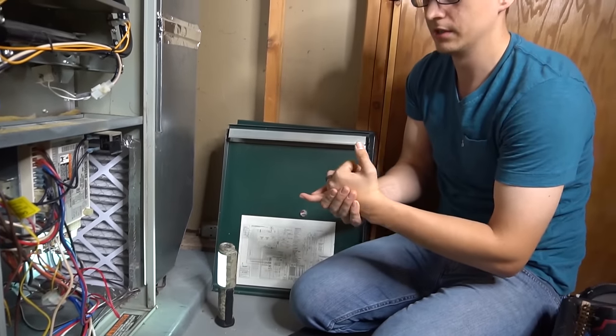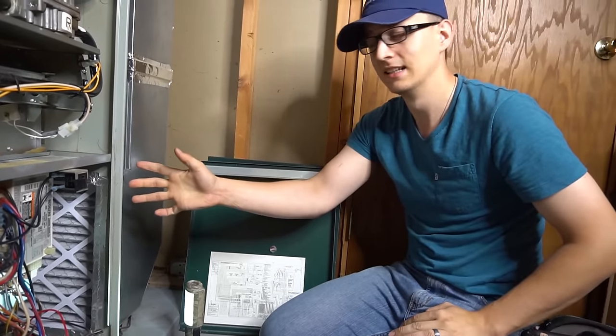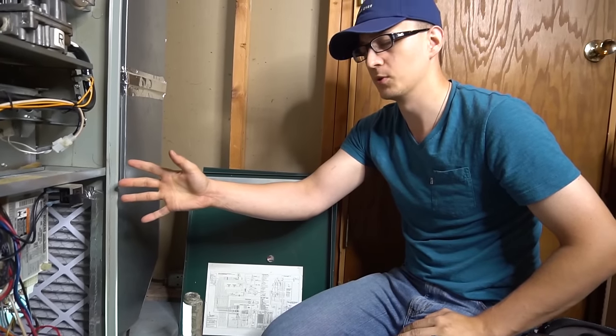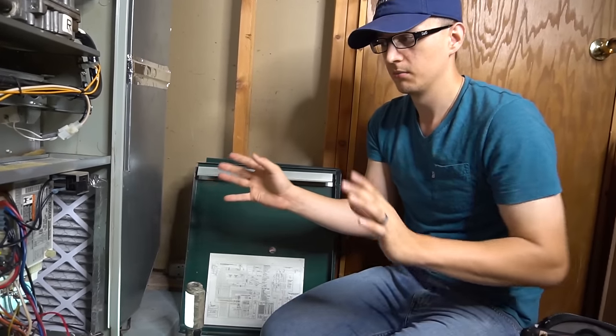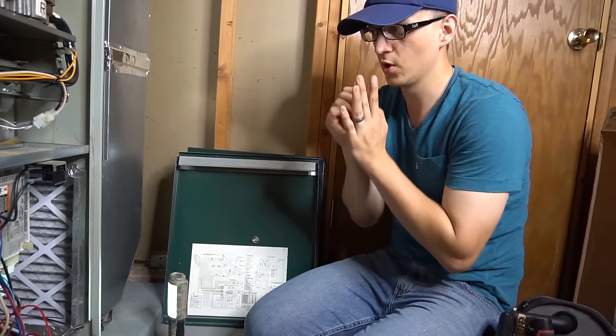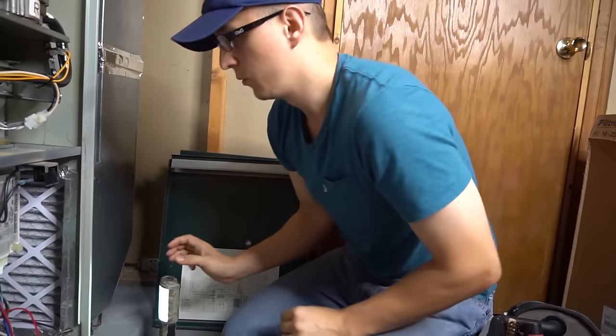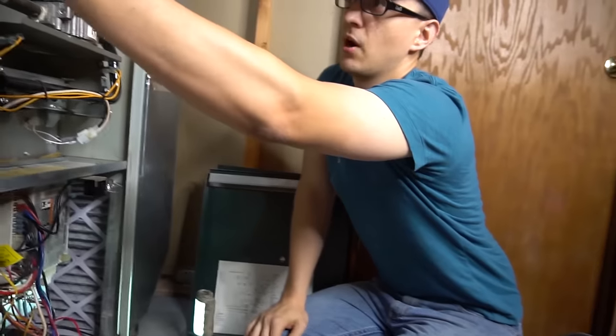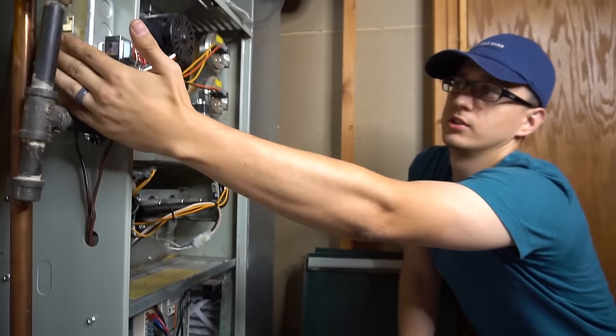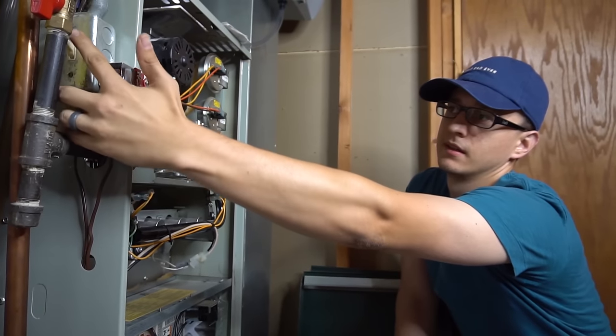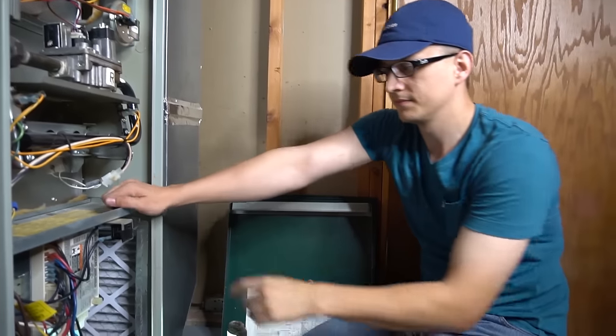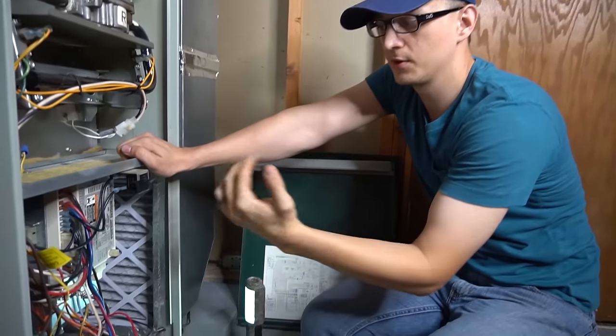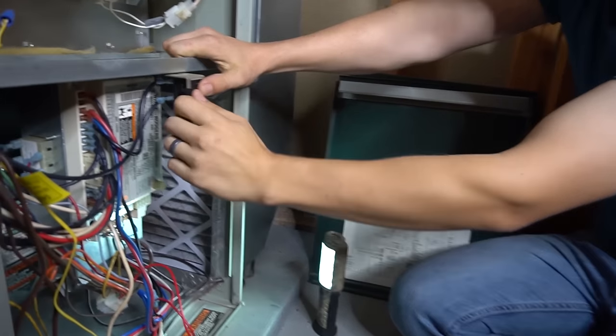So if your capacitor is good and your motor is hot, then almost guaranteed that you need a new motor. But we don't want to guess. So to know for sure, what you want to do is turn that power back on. We're going to do this test with the power on. Turn the power back on. Take off your furnace doors. Make sure your door switch is taped.